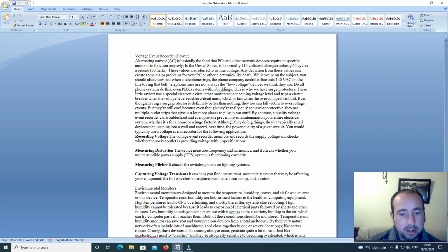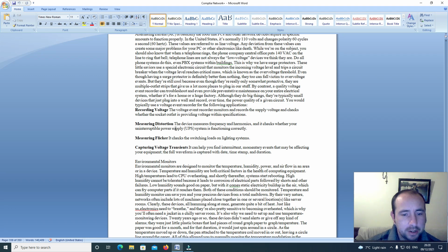You will typically use a voltage event recorder for the following applications: recording voltage, where it monitors and records the supply voltage and checks whether the socket outlet is providing voltage within specifications; and measuring distortion, where the device measures frequency and harmonics and checks whether your uninterruptible power supply system is functioning correctly.